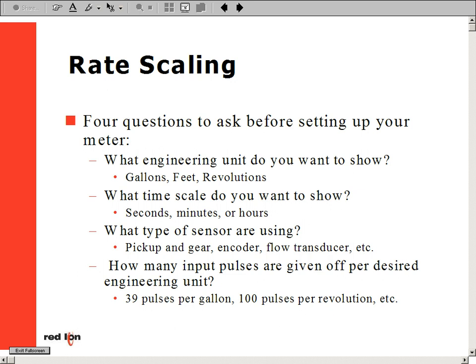Our equation for determining the rate input is: rate display times pulses per engineering unit, over desired time factor. When we are programming our rate meter, the rate input value and the rate display value are entered. The rate display, or desired reading, should be set at the fastest rated speed for your application. Our time factor is used to determine what scale we are measuring at — it can be in seconds, minutes, hours, or so on.